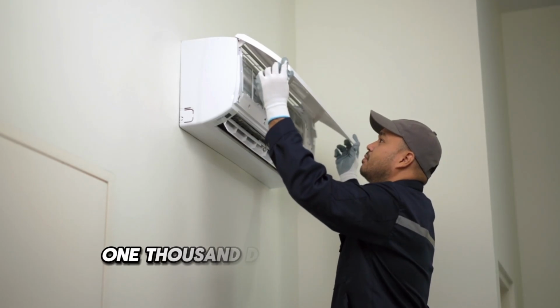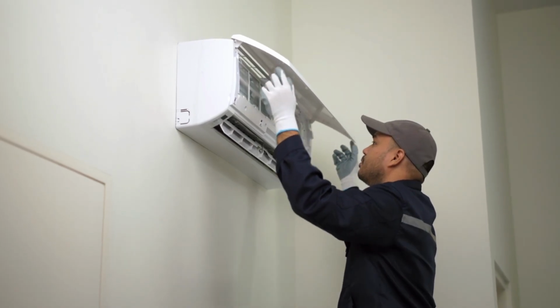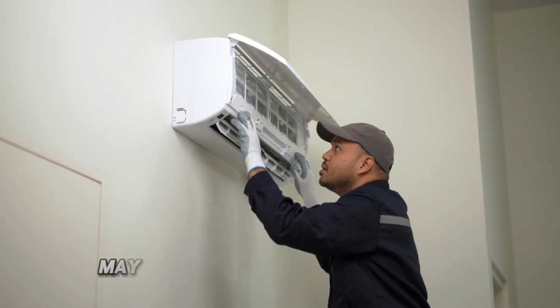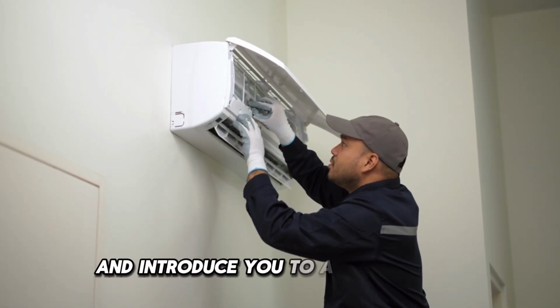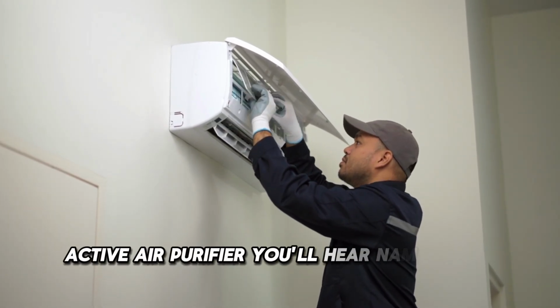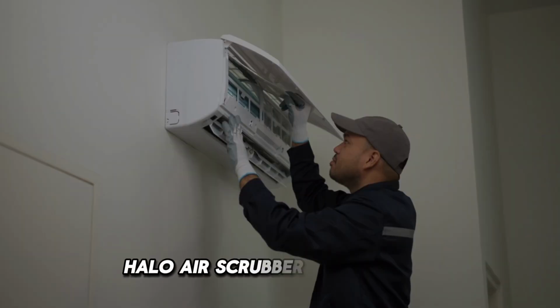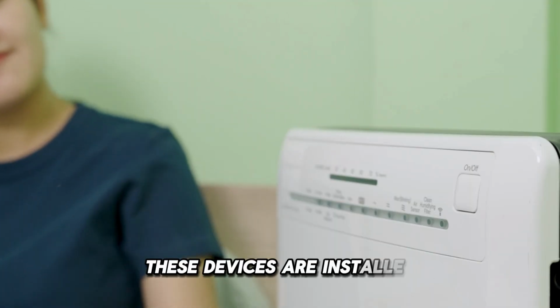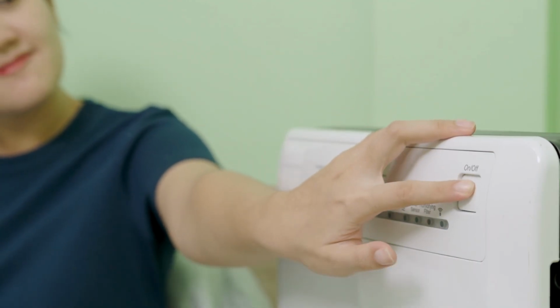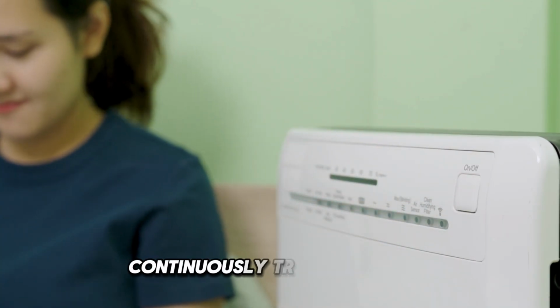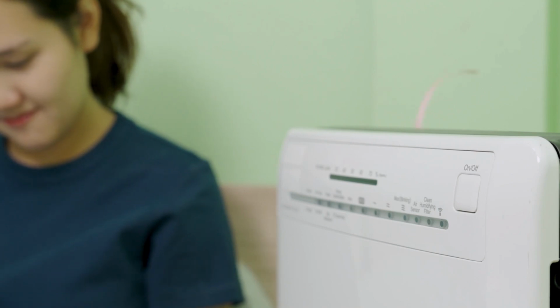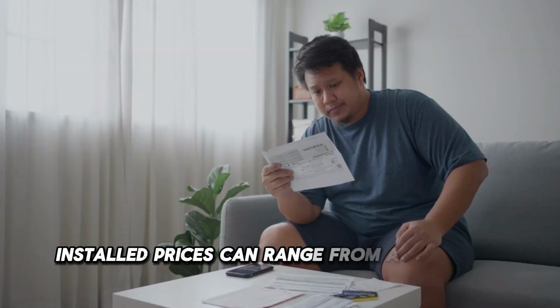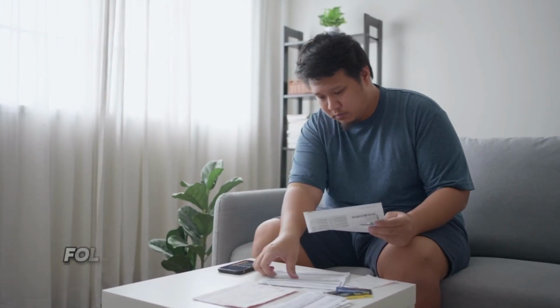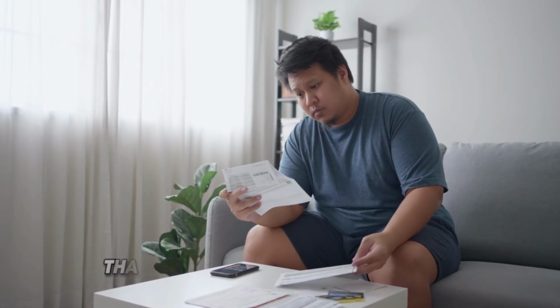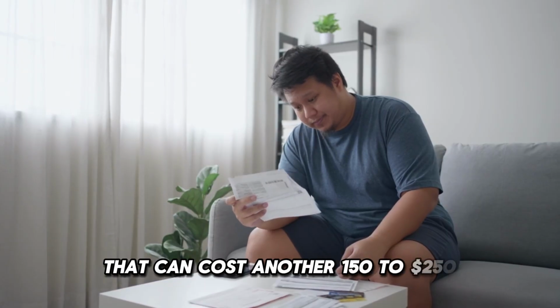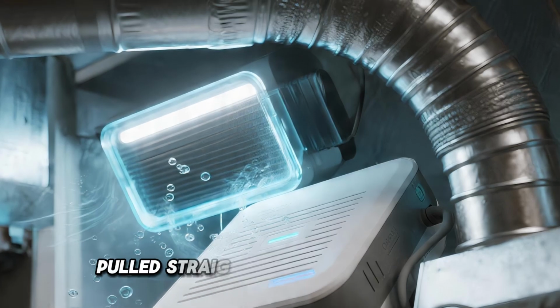2. The $1,000 machine that manufactures peroxide. Eventually, an HVAC sales technician may sit down at your kitchen table and introduce you to a whole home active air purifier. You'll hear names such as REME Halo, Air Scrubber, or iWave. These devices are installed directly into the main supply ductwork and are marketed as systems capable of continuously treating the air throughout your entire home. Installed prices can range from around $600 to $1,800, followed by replacement cells every few years that can cost another $150 to $250. It sounds like technology pulled straight out of a spacecraft.